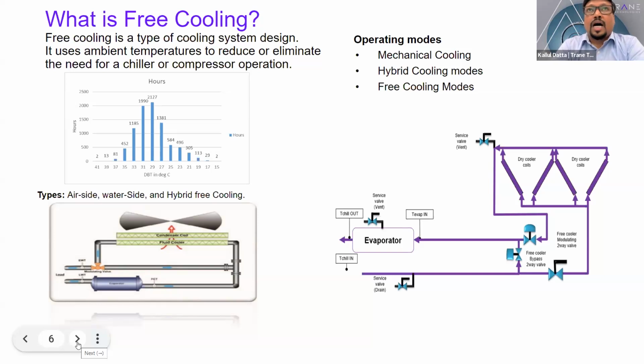Now, I have made a bar chart which shows the free cooling hours for a typical city in India. Why is it so important? Before selecting a chiller or a product designed for a waterside economizing system, we have to make sure that sufficient free cooling hours are available in those particular conditions. That means the climatic condition has to be very favorable in order to get the maximum output from the chillers.